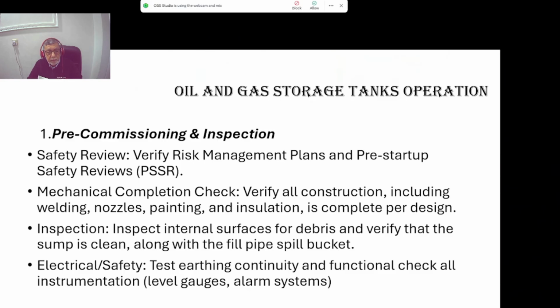Pre-commissioning and inspection. First is safety review, verifying risk management plans and pre-startup safety review. Mechanical completion check. We have to check everything about construction, including welding, nozzle, painting, and insulation, is complete as per design. Inspection. Inspect internal surface for debris and verify that the sump is clean, along with the fill pipe spill bucket. Electrical safety test, earthing continuity, and functional check of all instrumentation, level gauge, alarm system, and everything.